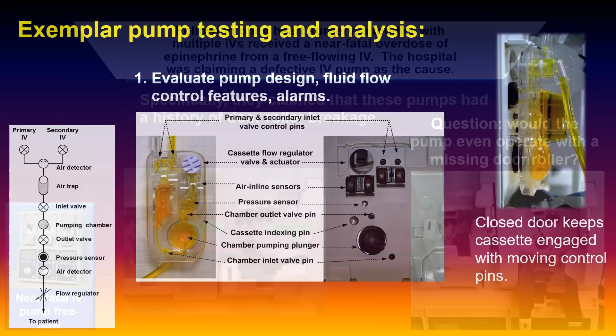So they went through the whole thing, really going through these devices independently. You find this is a really sophisticated little machine—a really sweet device in terms of the flow path the fluids have to go through, the alarms and sensors. There are maybe 30 different alarm conditions these pumps would go into.